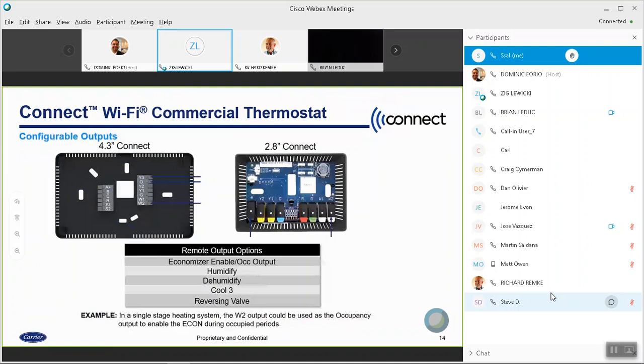Okay, these are the outputs. The 2.8 has two universal or reprogrammable outputs. The 4.3 has three. So any of those, in the case of the 4.3, the Y3, the O, and the W2, if those aren't used for, let's say, cooling 3 or heating or second stage of heating, you can basically assign one of these functions to it. Things like economizer, humidity, dehumidification, cool 3, or reversing valve can be assigned to any of these terminals. Same thing for the 2.8, but you're limited to two terminals. The asterisk terminal and the W2 can be reassigned to one of those functions.